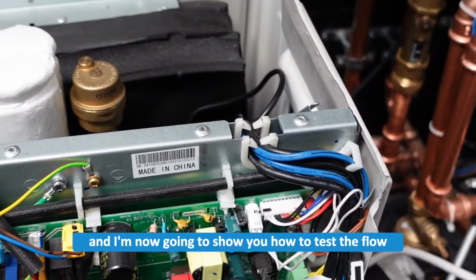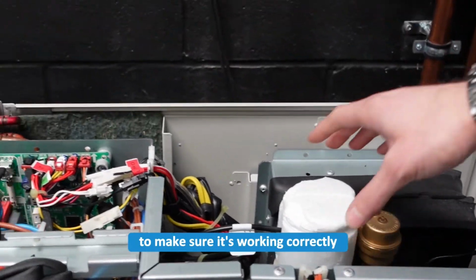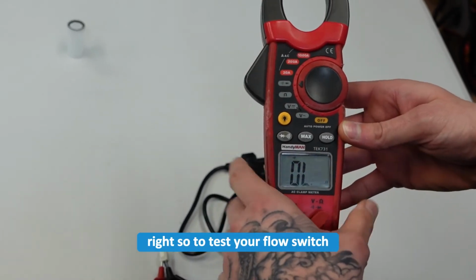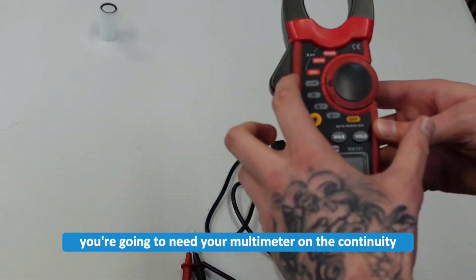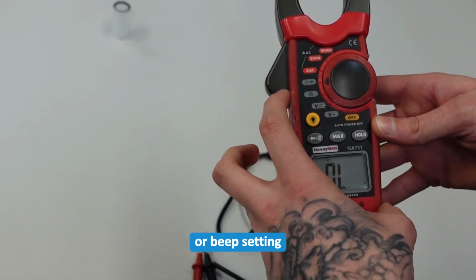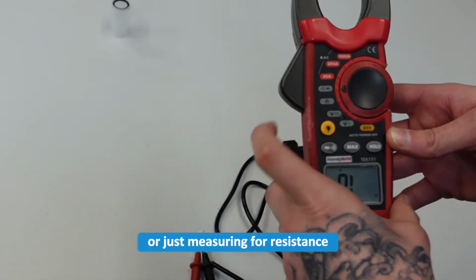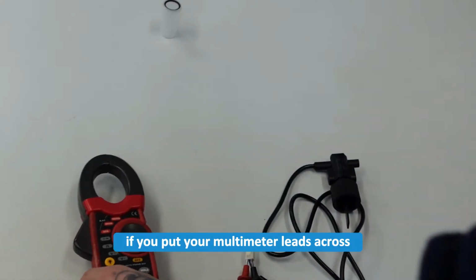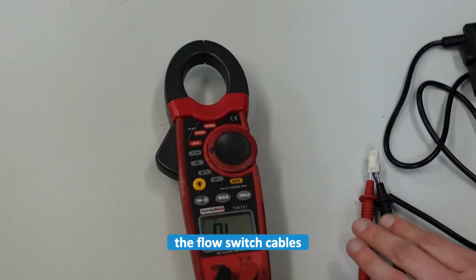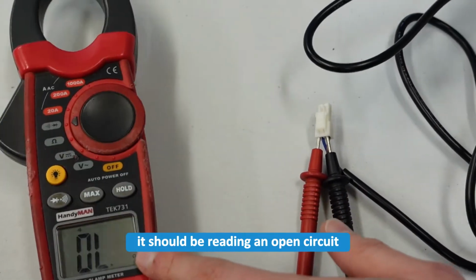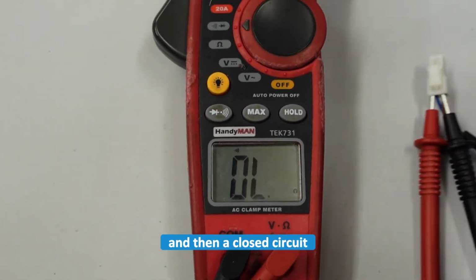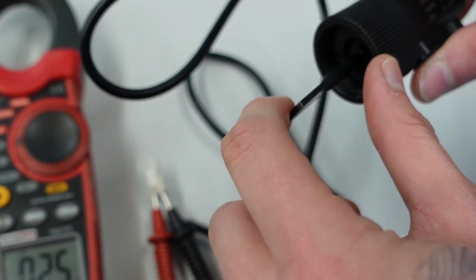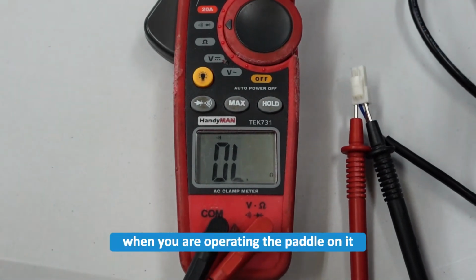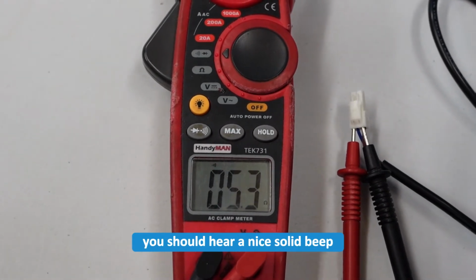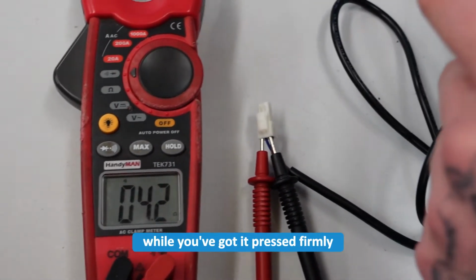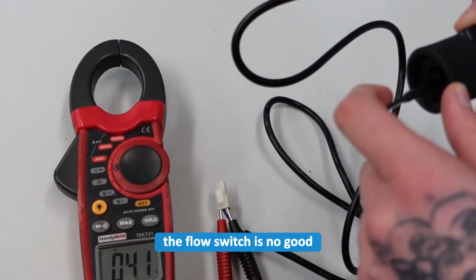And I'm now going to show you how to test the flow switch for continuity to make sure it's working correctly. Right, so to test your flow switch, you're going to need your multimeter on the continuity or beep setting, or just measuring for resistance. And what you'll see is if you put your multimeter leads across the flow switch cables, it should be reading an open circuit when you're not operating the paddle, and then a closed circuit when you are operating the paddle on it. And when you put the beep on, you should hear a nice solid beep. If it's cutting in and out while you've got it pressed firmly, the flow switch is no good.